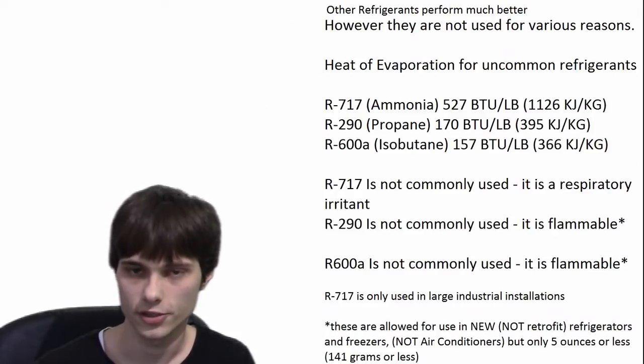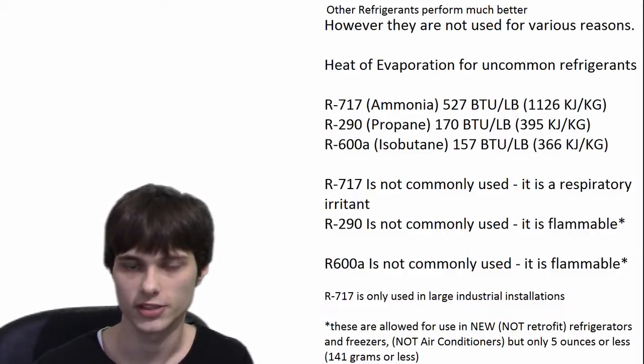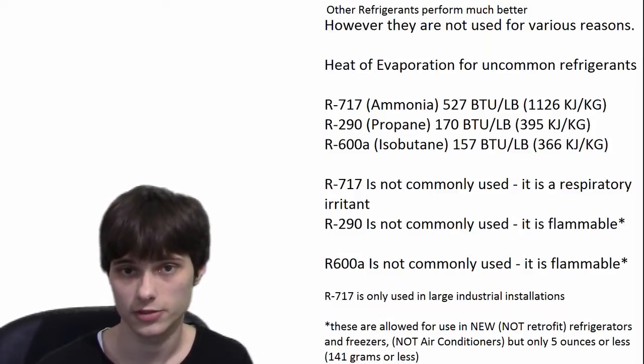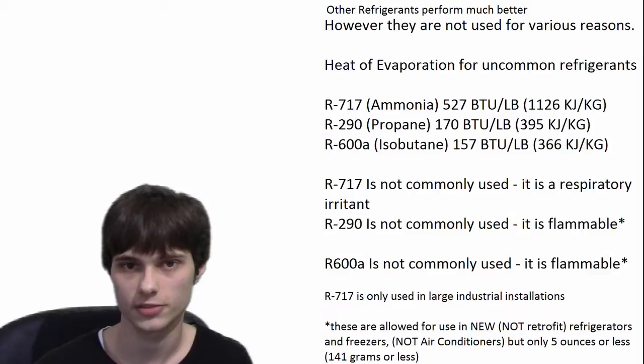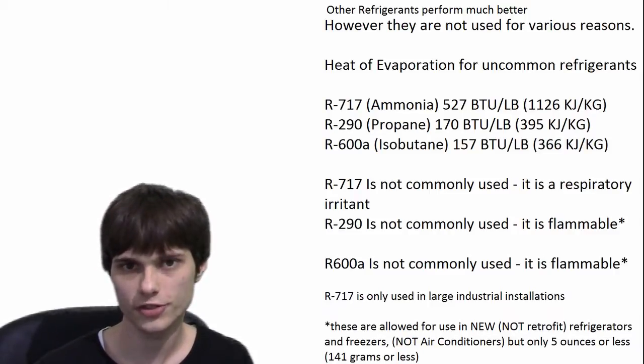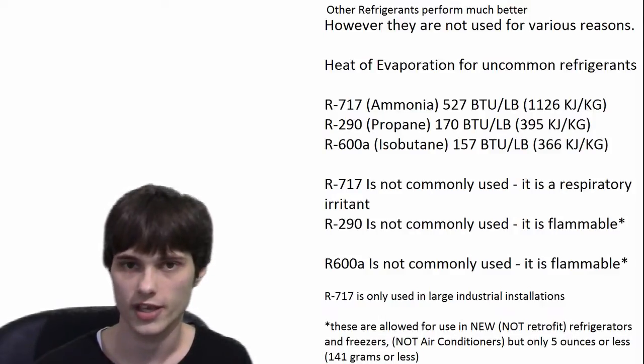Refrigerants that aren't commonly used — and I'll show you some of those up here — they perform much better. But for one reason or another, they're not actually used. Hydrocarbons like propane and isobutane have higher heats of evaporation, so if you used those, you wouldn't have to pay as much to circulate them through the system. But unfortunately, you can't use those — it's illegal to use those in an air conditioner because they're flammable and they're deemed too dangerous to use. Ammonia is a great performer, but again, you can't use it. The reason is simple: it's a respiratory irritant. You get one little whiff of that, you won't be able to breathe, and you could even pass out. Although it is used in some very large industrial and commercial applications, you still can't use it in your home.